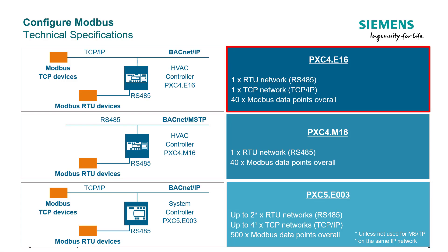PXC4-E16: The Ethernet version supports both RTU and TCP/IP Modbus devices. The RTU devices can be connected via the RS-485 connector onboard, whereas for TCP/IP devices, one of the Ethernet switches can be used. The total number of Modbus data points supported is 40.